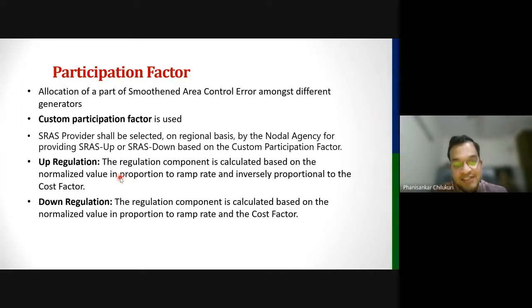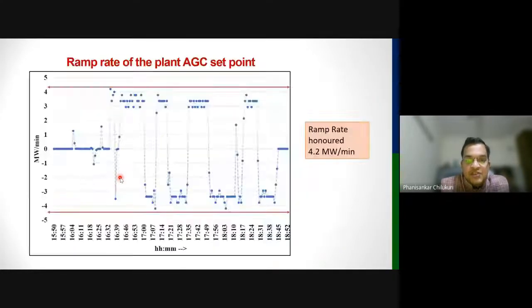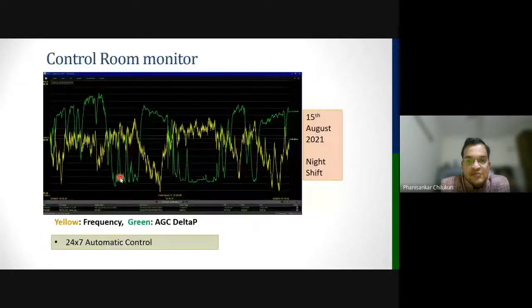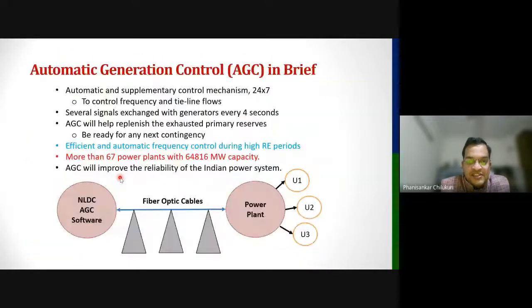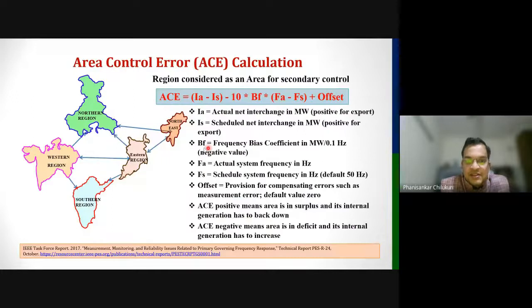So we harness the diversity that is there in the Indian power system. To the extent possible, we operate in constant frequency mode. Sometimes when there is congestion, we operate in tie line bias mode also. The bias which we take for K delta F is based on the frequency response characteristic of that region.